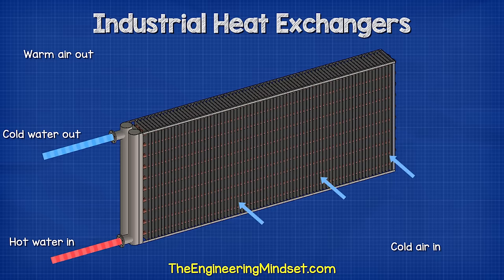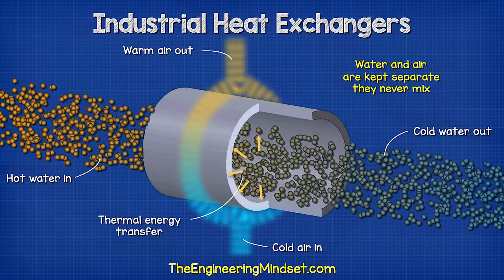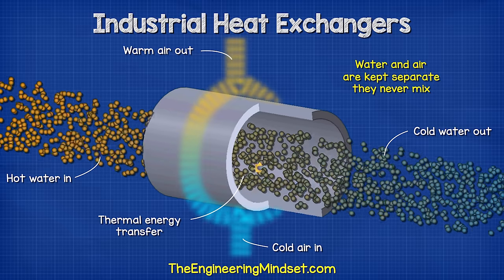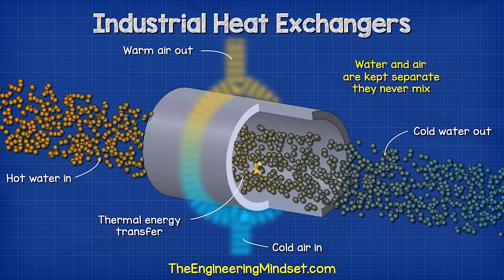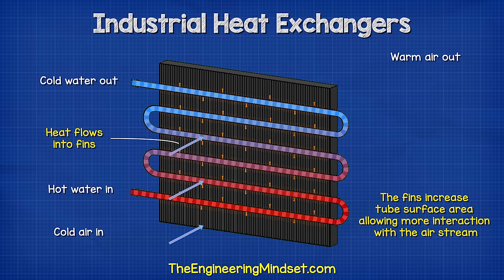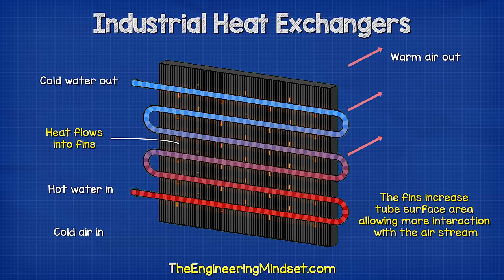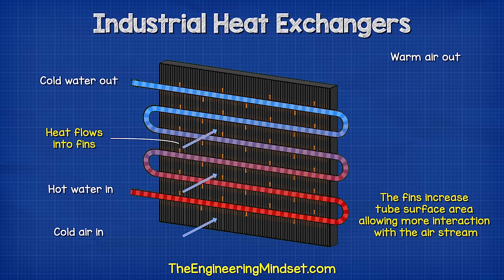The other fluid — for example, ambient air — will pass over the outside of the tube, between the fins. The two fluids will never mix. The heat passes from the hot water through the tube wall and into the air. The fins increase the surface area and allow more interaction with the air stream, which improves the heat transfer.